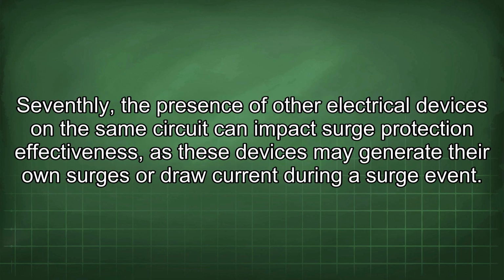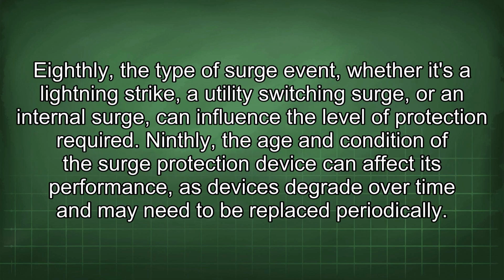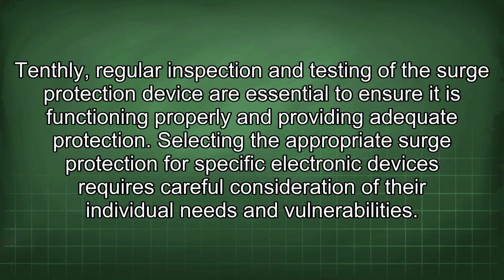Seventhly, the presence of other electrical devices on the same circuit can impact surge protection effectiveness, as these devices may generate their own surges or draw current during a surge event. Eighthly, the type of surge event, whether it's a lightning strike, a utility switching surge, or an internal surge, can influence the level of protection required. Ninthly, the age and condition of the surge protection device can affect its performance, as devices degrade over time and may need to be replaced periodically. Tenthly, regular inspection and testing of the surge protection device are essential to ensure it is functioning properly and providing adequate protection. Selecting the appropriate surge protection for specific electronic devices requires careful consideration of their individual needs and vulnerabilities.